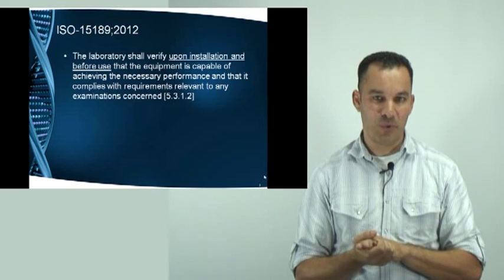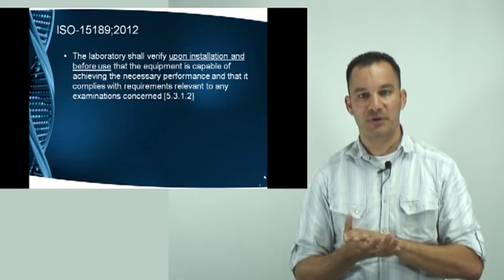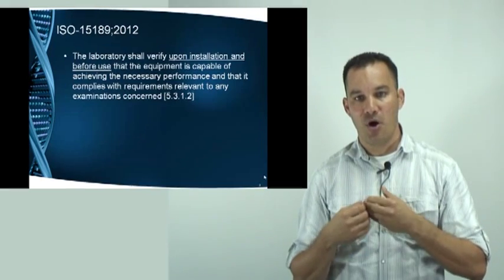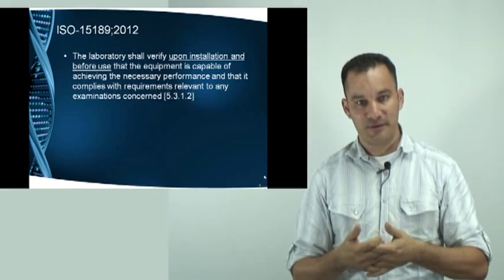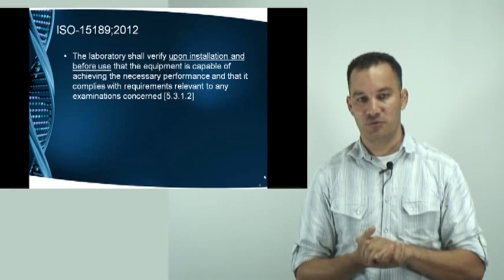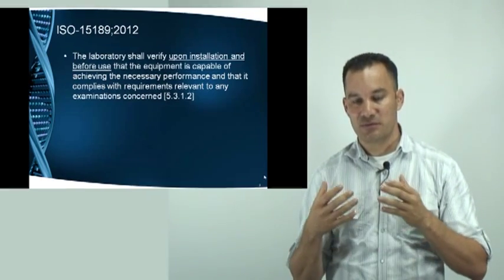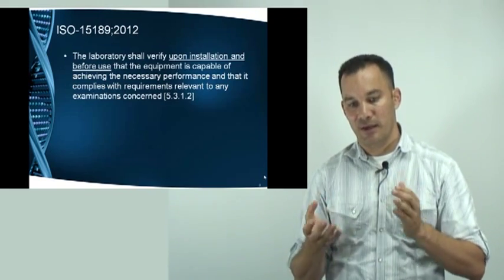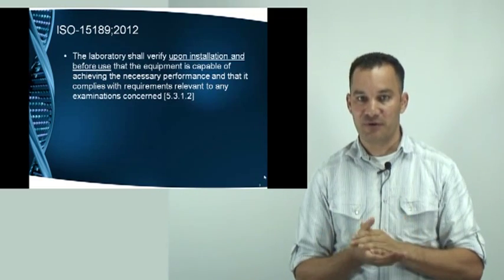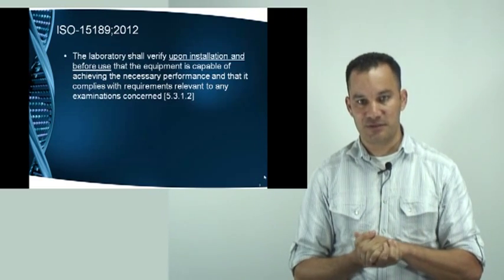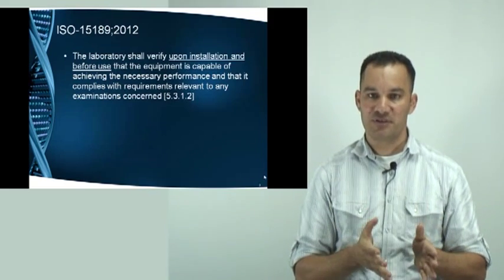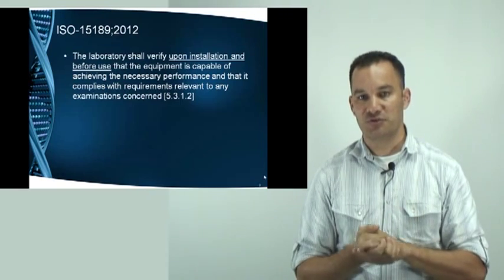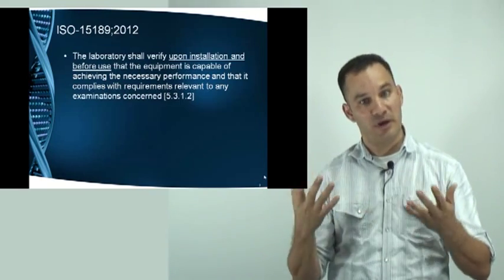So here we have the first requirement: as a laboratory, we should be capable of demonstrating that the instrument that has just arrived into our laboratory is capable of performing the way it should. This verification should be done upon installation and before we start producing results for patients — it's not something that we can do afterwards.